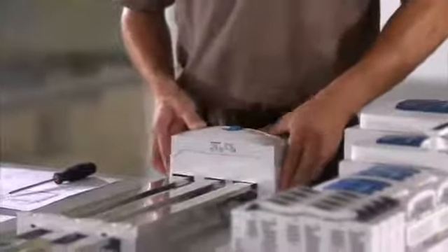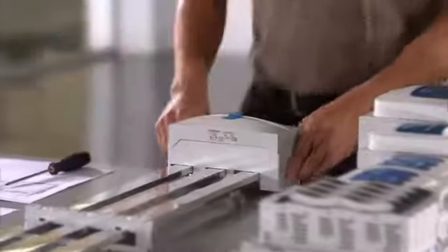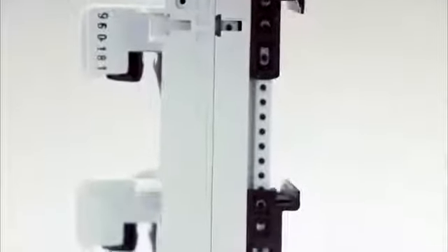However, it is not just fuse devices that can be mounted on the bus bar system. The development of Woehner's proprietary Equus adapter technology enables motor starter combinations as well as circuit breakers and contactors to be used on the bus bar system.